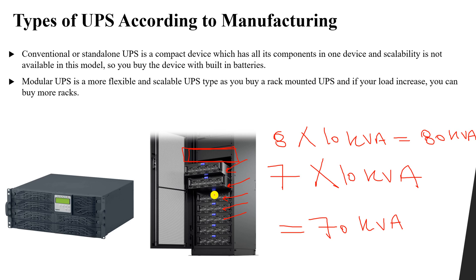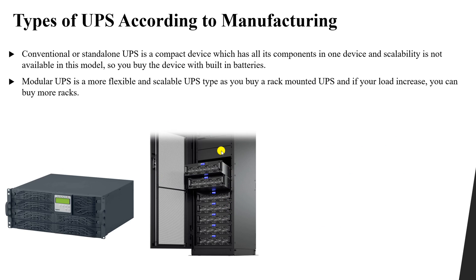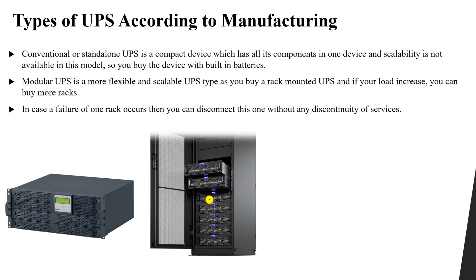The modular UPS is scalable — you can change its rating by adding or removing modules, unlike the conventional UPS which has a fixed rating. This is important because sometimes our load will increase due to future expansion. In that case, we simply add more UPS modules. Another big advantage is that if one module has a problem, you can remove that unit and the rest of the system will continue to operate normally without any discontinuity in service.